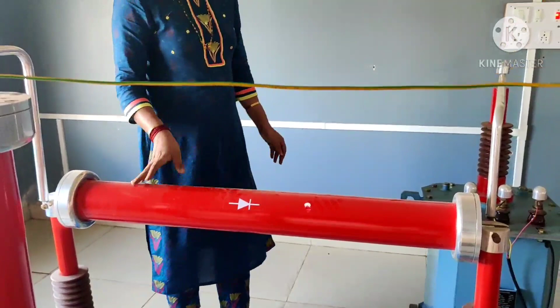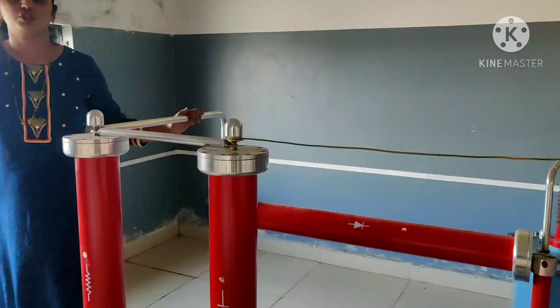So this is the configuration of the high voltage test kit. We first do HVAC, testing for sphere-to-sphere uniform gap. I have two spheres and this wire connected so that the 50 kV AC we are getting here is directly applied to this electrode. We need to test the breakdown strength of air, acting as an insulator between these two electrodes, so first we need to vary the gap length using this part.